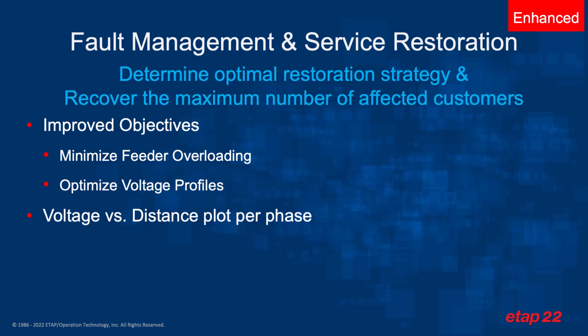Fault management and service restoration allows us to determine the optimal restoration strategy and recover the maximum number of affected customers during a forced or unplanned outage. Fault management and service restoration has improved objectives such as minimization of feeder overloads and optimizing the voltage profiles. And it also includes a new plot allowing us to plot voltage versus distance per phase.